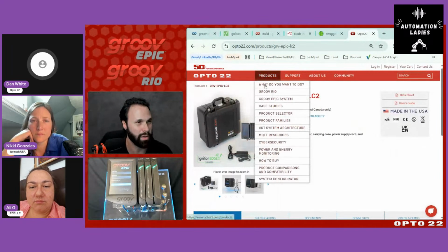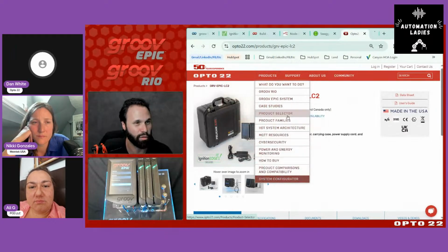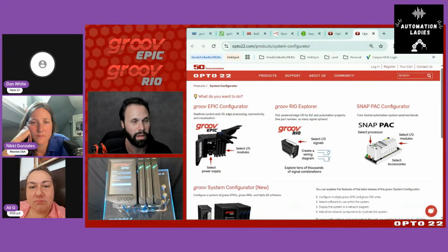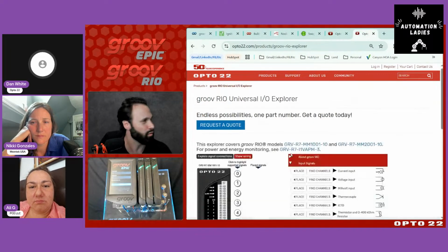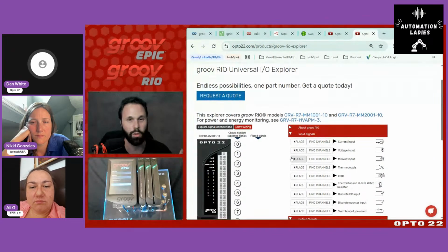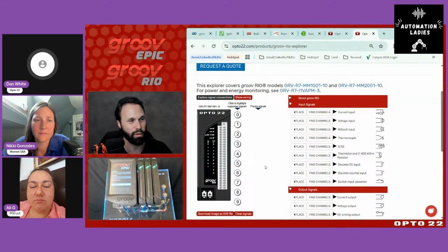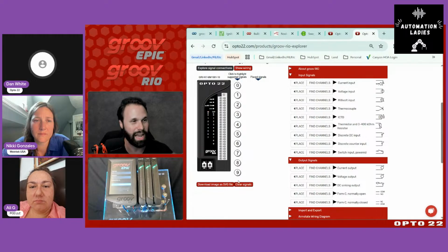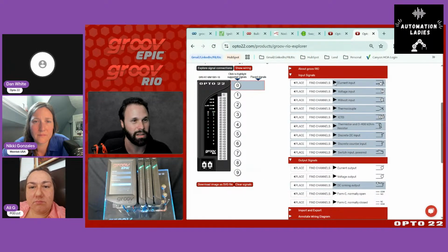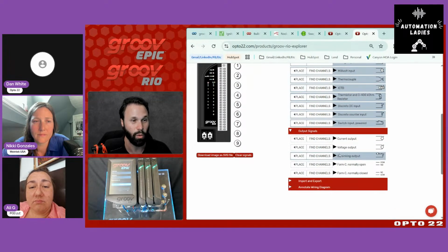It's a lot like our groov RIO—I always go to the groov RIO, what we call our Explorer, because it's just a single remote IO block. Within that groov RIO you've got 10 IO points. Two of them are just relay outputs, down here at the bottom. But these other ones can be configured as current input, voltage input, millivolt—all the different input types, or it could even be an output.